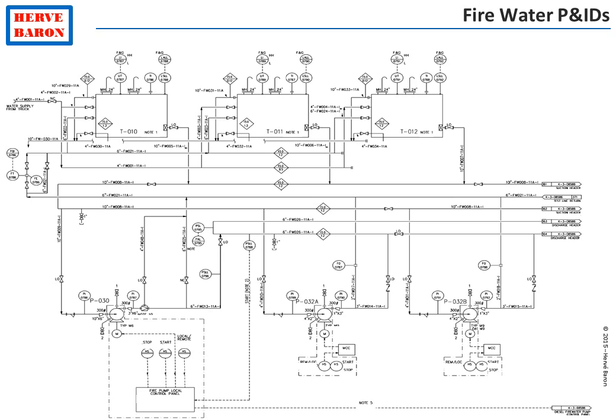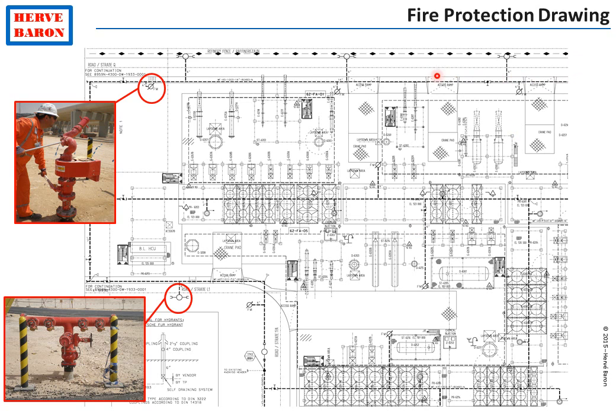The fire water system is designed by safety by issuing P&IDs which show fire water storage, pumping, and distribution. The system is also defined by safety by issuing its routing drawing called the fire protection drawing. This drawing shows the route of the fire water distribution network — a ringed network that circles the facility and is provided with isolation valves at regular distances so that a part of it can be isolated and repaired without affecting the remainder.